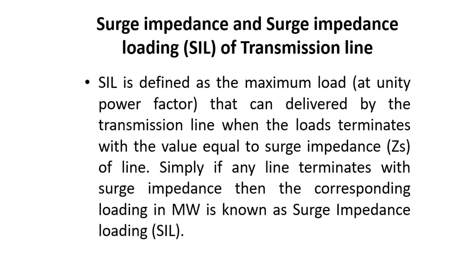So students, in the hardware practical you will see that we have different loads connected with our transmission lines, and we will find at which value the load becomes equal to the surge impedance of the transmission line. At that point you will see that the reactive power consumed by the line is almost zero, that is negligible, and the maximum loading occurs because the maximum megawatt, the real power, is transmitted in that case.